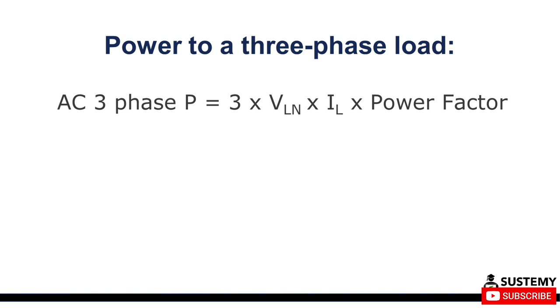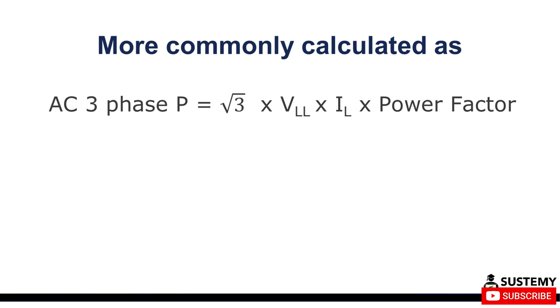connection. The power delivered to a 3-phase load is equal to 3 times the line to neutral voltage times the line to neutral current. However, as the voltage for 3-phase power is often given as the line to line voltage, the formula for 3-phase power then changes. 3-phase power equals the square root of 3 times the line to line voltage times the line current times the power factor.